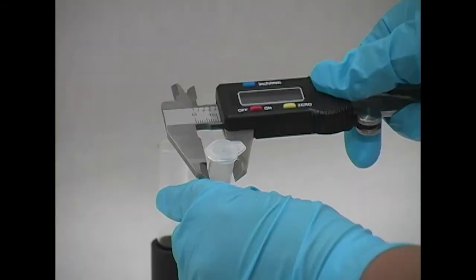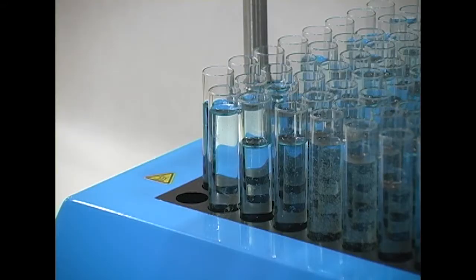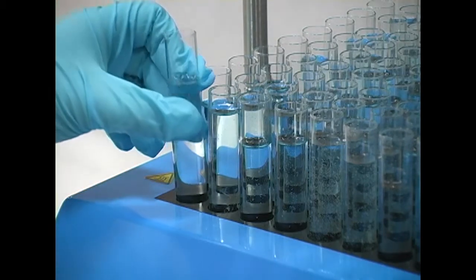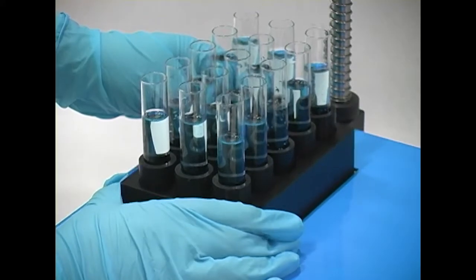Do not worry about oversizing the dimensions once you have measured your test tubes. Organomation technicians will drill the inserts slightly wider than the diameter of your sample tubes to allow for thermal expansion so your test tubes will not get stuck in the instrument.